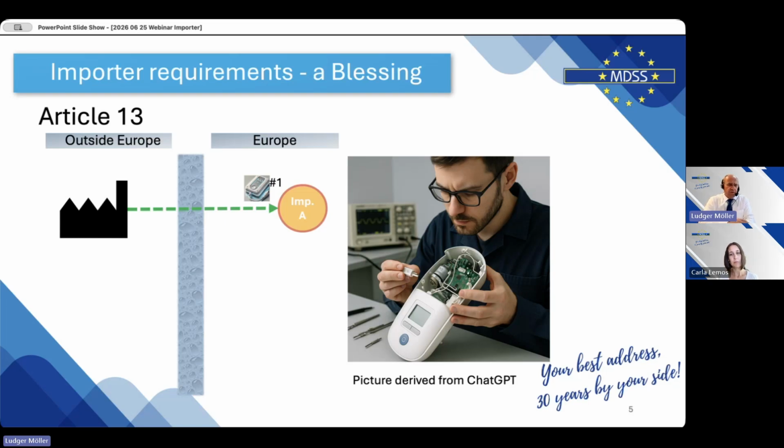And who was responsible? The importer actually, who did that, and he put then later on his name on the product. And he became the manufacturer. So the role of a manufacturer can easily be done by slapping your name on the product. With the importer, there may be a couple of other aspects. But again, it's a blessing because it's written down.